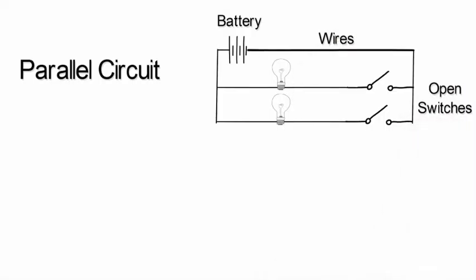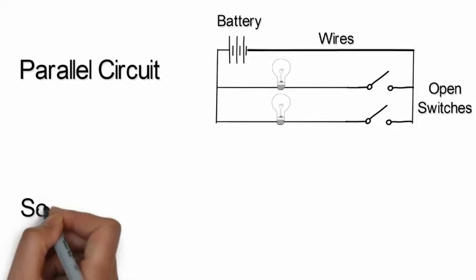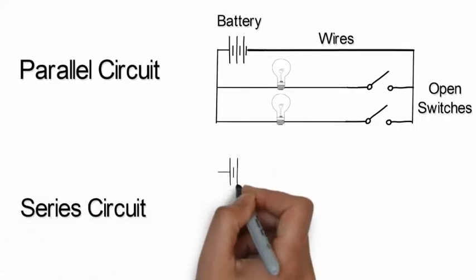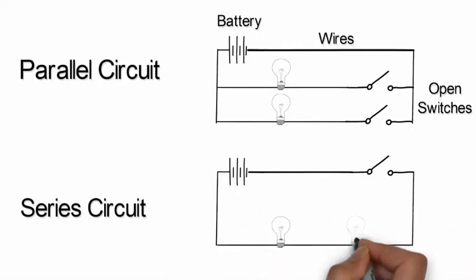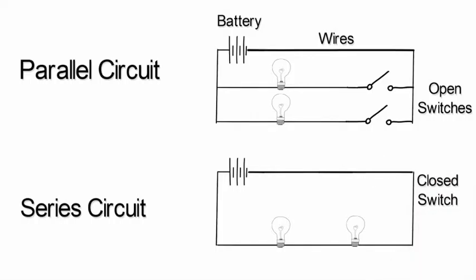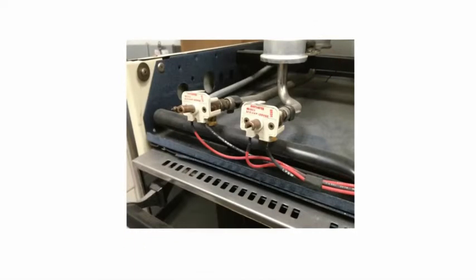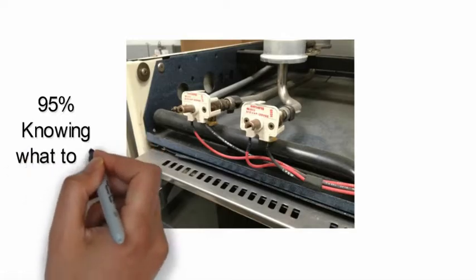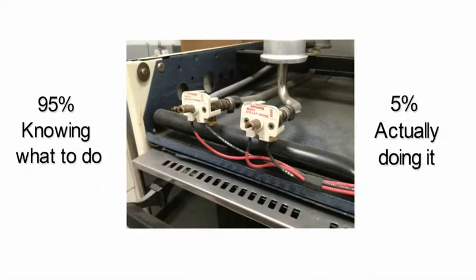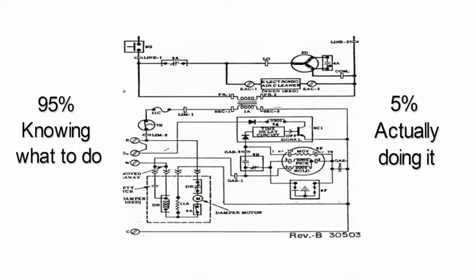Looking at individual circuits in parallel is like looking at any simple circuit. Most control circuits, on the other hand, are connected in series with the components they are controlling. A switch that is normally open will keep any component in series with it off until the switch is closed. All switches connected in series must be closed for a connected load to operate. Switches and controls are important circuit elements to understand when looking at a wiring diagram. Diagrams are visual floor plans for the electrical parts of a system. Taking the right action with an electrical circuit is 95% knowing what to do and 5% actually doing it. The wiring diagrams make the first part much easier to do.